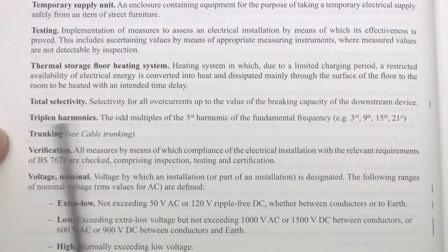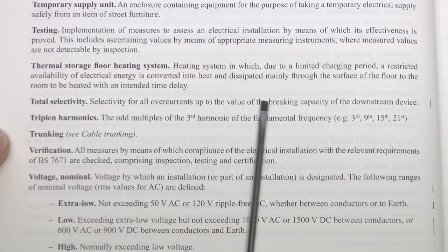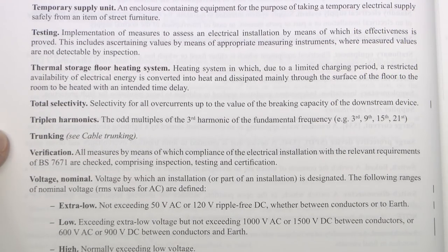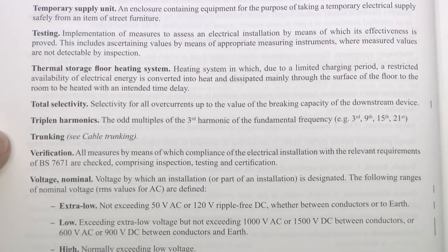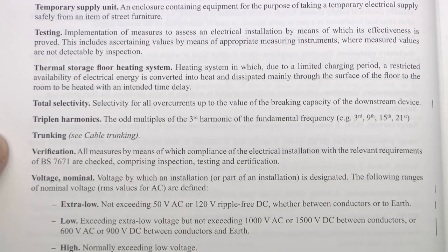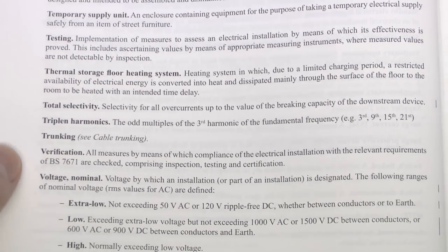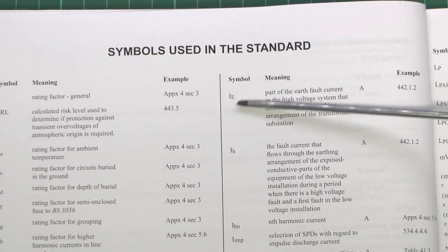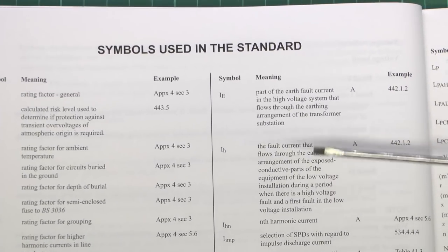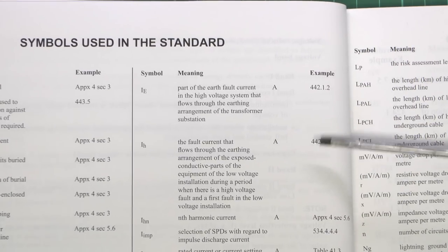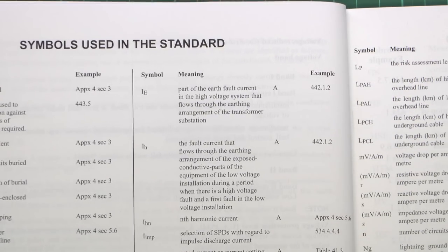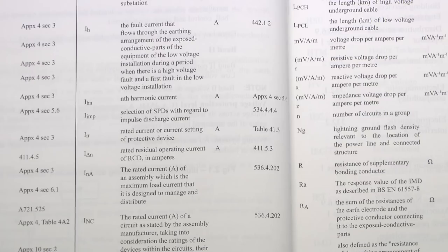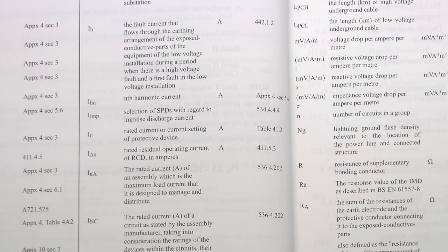And the final new one is Total Selectivity, which is selectivity for all overcurrent up to the value of the breaking capacity of the downstream device — compare that with Partial Selectivity which we saw on the previous page. And again, it fits in with the whole idea that it was called Discrimination before and now it's called Selectivity instead. Now that's it for the actual definitions themselves. There are a few changes within the symbols section, but most of these just refer to regulation numbers that have been renumbered, so the actual definitions are pretty much the same.